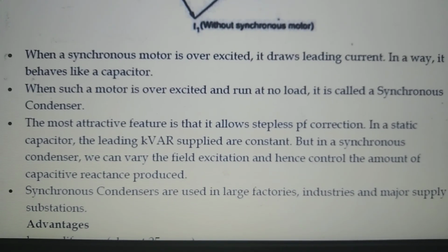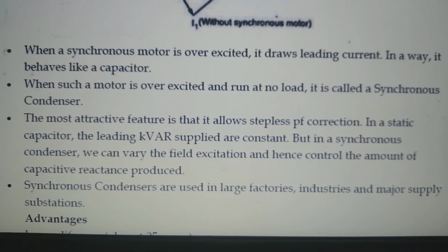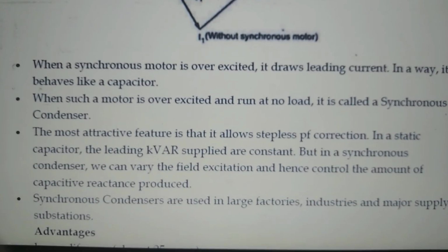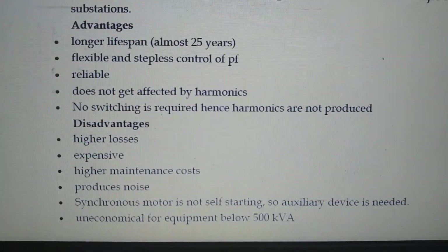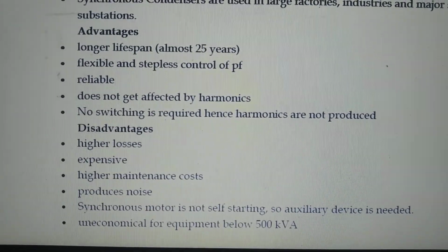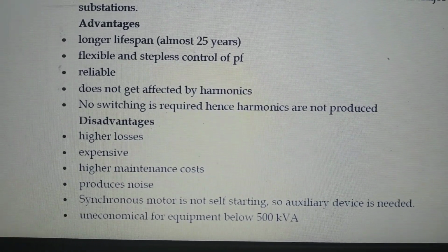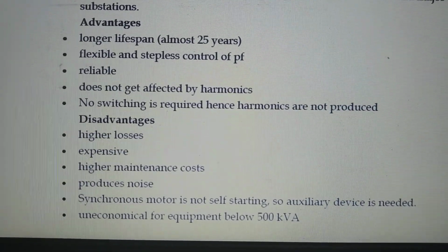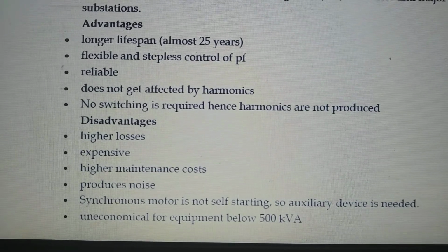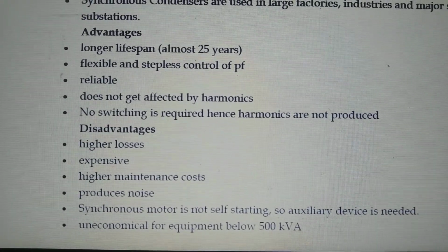Synchronous condensers are used in large factories, industries, and major supply substations. The synchronous condenser method also has some advantages and disadvantages. Advantages are longer lifespan, flexible and stepless control of power factor, more reliability, not affected by harmonics, and no switching is required, hence harmonics are not produced.